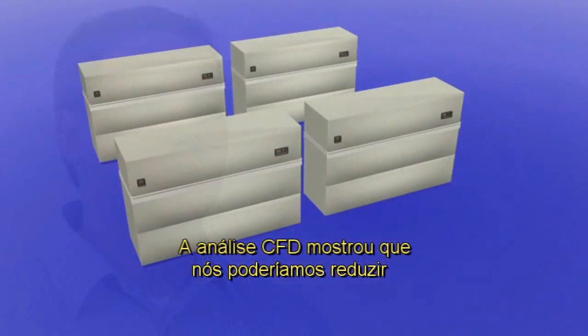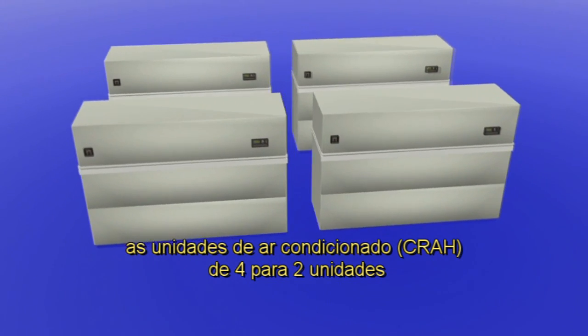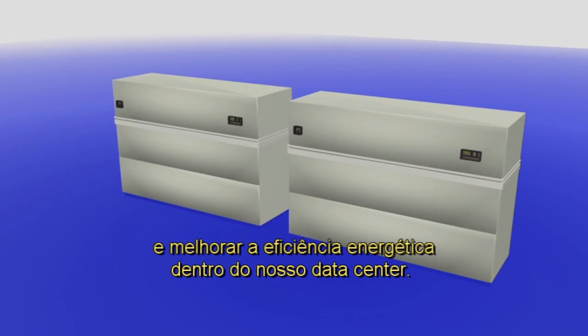The CFD analysis showed we were able to reduce our CRAH units from four down to two units. This would meet our thermal needs and improve our energy efficiency within the data center.